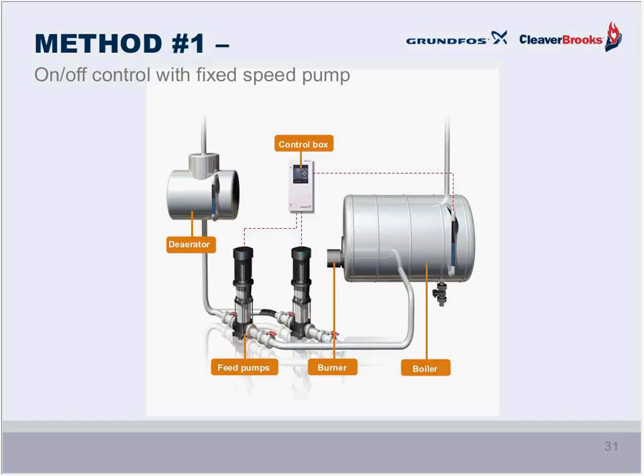So here's the first control method. It's simple on-off control. The control box is responding to level in the boiler to cause the pumps to turn on and turn off according to the need. That sensor is mounted on the boiler, which Steve mentioned. Could be float-actuated set of switches, like Steve showed you.